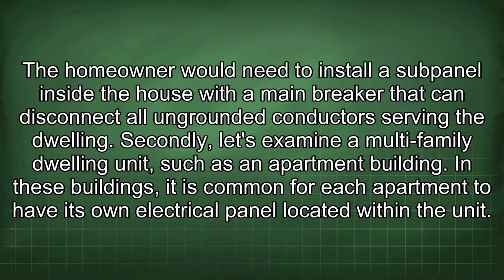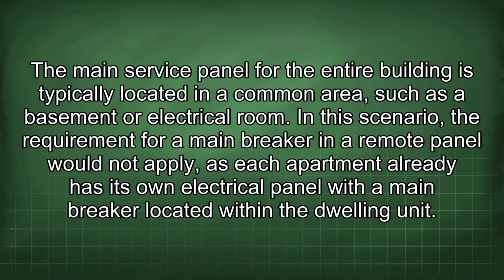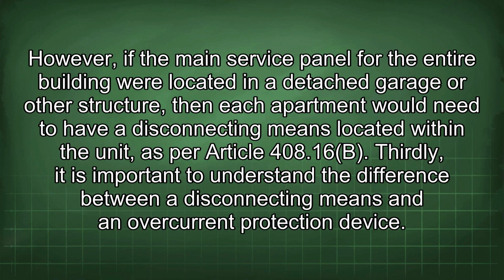In these buildings, it is common for each apartment to have its own electrical panel located within the unit. The main service panel for the entire building is typically located in a common area, such as a basement or electrical room. In this scenario, the requirement for a main breaker in a remote panel would not apply, as each apartment already has its own electrical panel with a main breaker located within the dwelling unit. However, if the main service panel for the entire building were located in a detached garage or other structure, then each apartment would need to have a disconnecting means located within the unit, as per Article 408.16b.